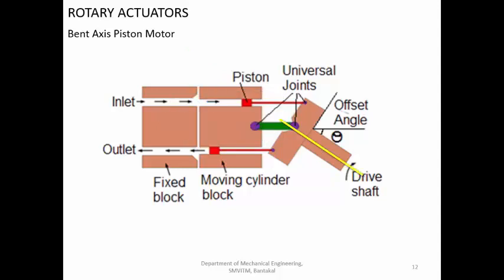The bent axis will provide the inclined surface on which the cylinder pistons can slide. Because the pistons cannot naturally slide, the cylinder block will rotate along with the piston as they slide downwards because of the action of the high pressure fluid. The main advantage of piston motors is they can generate very high torques within a very small size. They can generate the maximum amount of torque and can also operate at significantly high speed. The main disadvantage is their initial cost is very high as compared to other hydraulic actuators, so they are used only where very high power and torque are required.